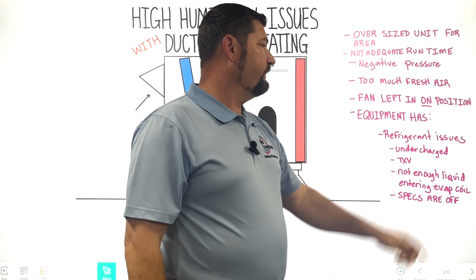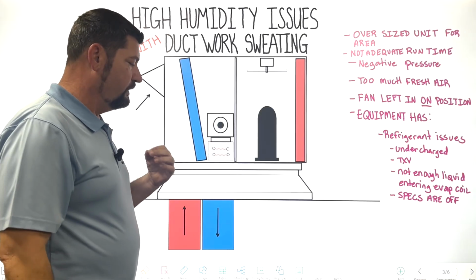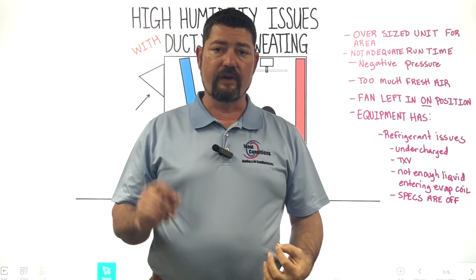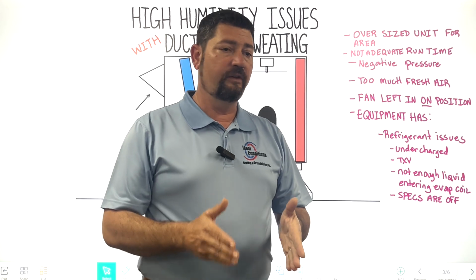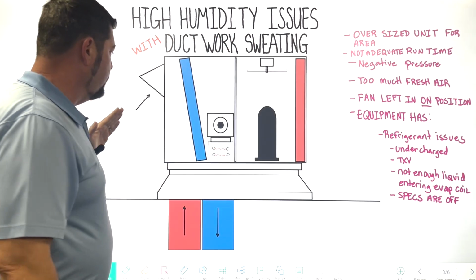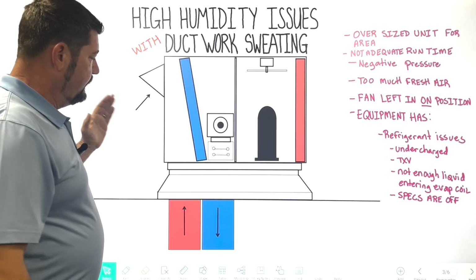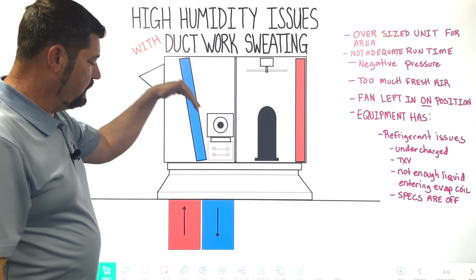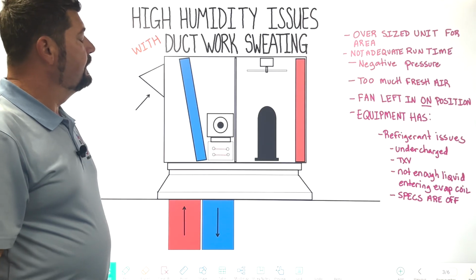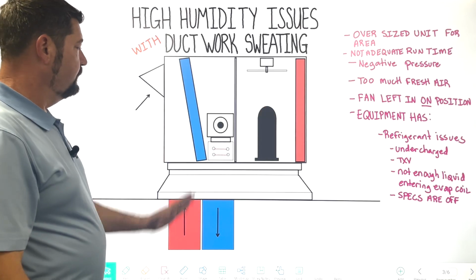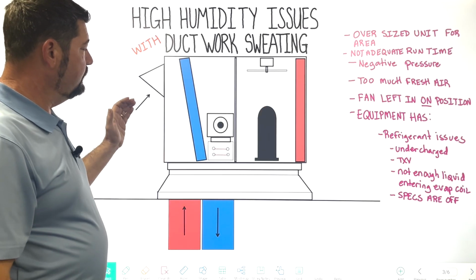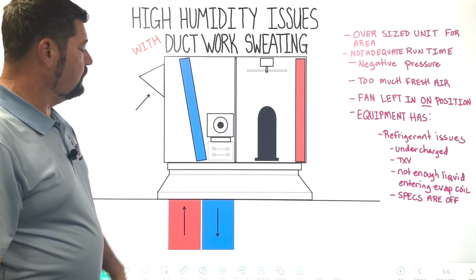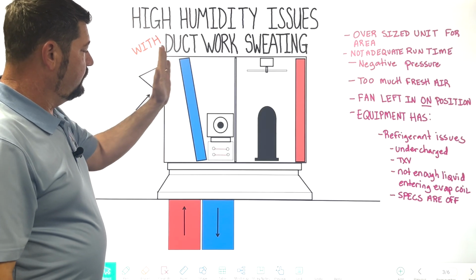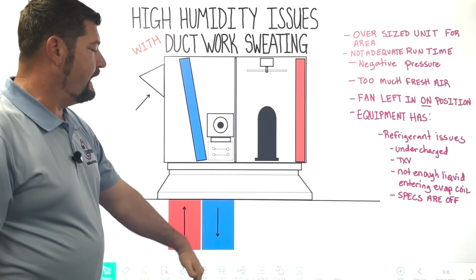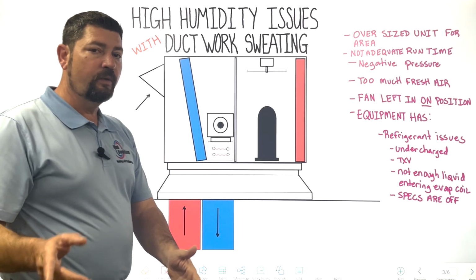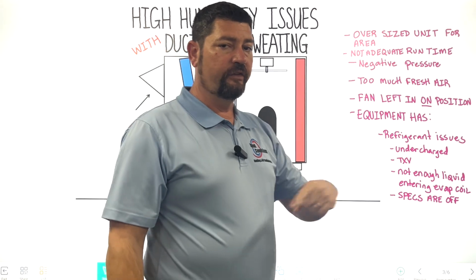If the fan is left in the on position, meaning the blower is left in the on position via the thermostat, you have auto and on. If that is left in the on position, then what happens is, remember, we're pulling air from our fresh air into the package unit, and we're putting that back into the building through our supply. And if our compressor is not running, providing us a cold coil that we can condense that humidity onto, then what will happen is, if that coil is not cold, that humidity is just going to be added to the structure in between the cycles of the system coming on and running.